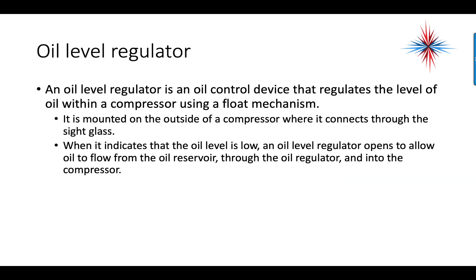An oil level regulator is an oil control device that regulates the level of oil within a compressor using a float mechanism. It's usually mounted on the outside of the compressor where it connects through the sight glass hole. When it indicates that the oil level is low, an oil level regulator opens to allow the oil to flow from an oil reservoir through the oil regulator and into the compressor.